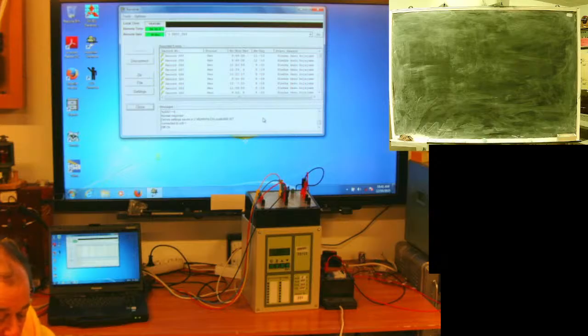Time setting from remote PC isn't enough. I don't know when someone will connect my device, and this doesn't ensure time discipline. This device uses an older approach: it has one binary input for time discipline. On a substation, a central clock should be installed. The central clock sends a pulse, one per minute, and this pulse zeroes the second counter on devices.